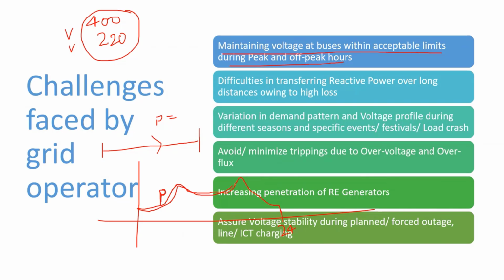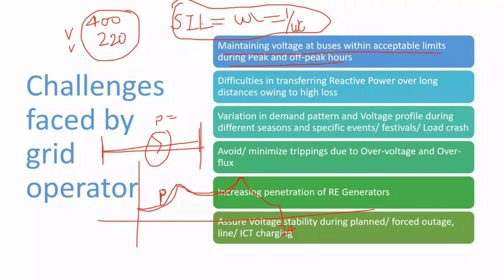Based on this power flow, how much reactive power will be generated is decided for this transmission line. If your transmission line is not loaded at its optimal loading, then it will either be producing reactive power or absorbing reactive power. So how is it done? We already know the term SIL, surge impedance loading, where omega L is equal to 1 by omega C. At surge impedance loading, there is no net reactive power generation. So you have optimal reactive power, the line is at the optimal voltage level, and you don't have to worry about the voltages.